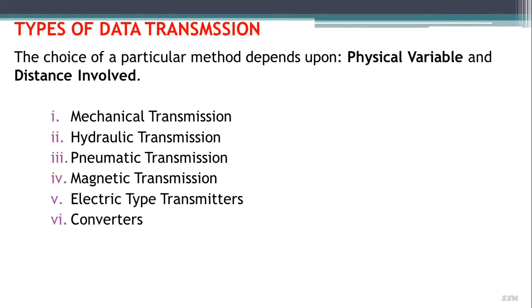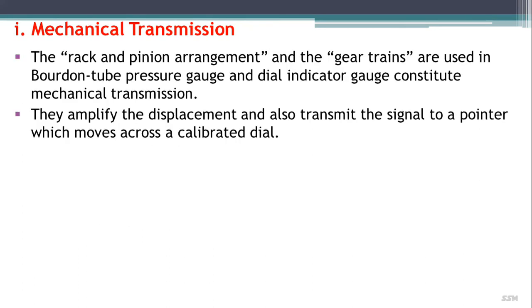The different types of data transmission are: mechanical, hydraulic, pneumatic, magnetic, and electric type transmitters and converters. Starting with mechanical transmission — the rack and pinion arrangement and gear trains are used in a Bourdon tube pressure gauge and the dial indicator gauge. They amplify the displacement into a transmitted signal to a pointer which moves across a calibrated dial.